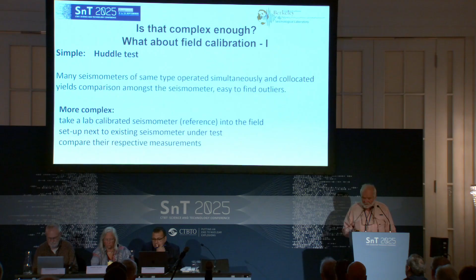We can also, of course, take seismometers calibrated in the lab and take them into the field and set them up next to an existing seismometer under test, so augment the seismic station if you want, and you compare the respective measurements. But this is an extremely invasive operation. You have to disturb the measurement because you're going into the seismic station and you open the doors of the vault. You see the steps of everybody walking around there. So it's a very invasive way of trying to see how the seismometer under test and the other elements of the seismic station work.